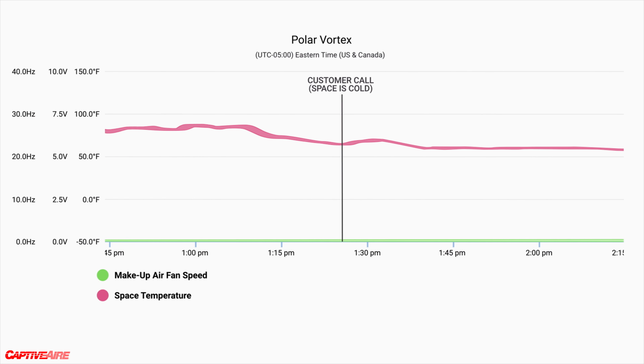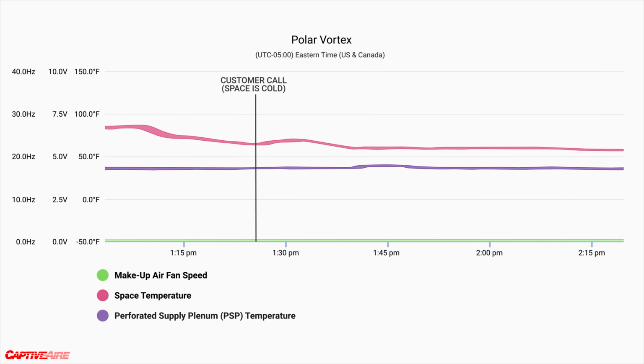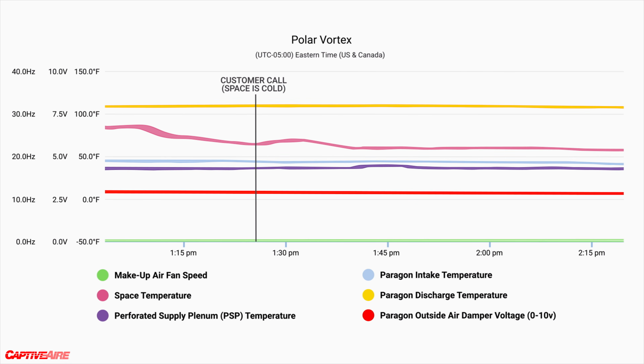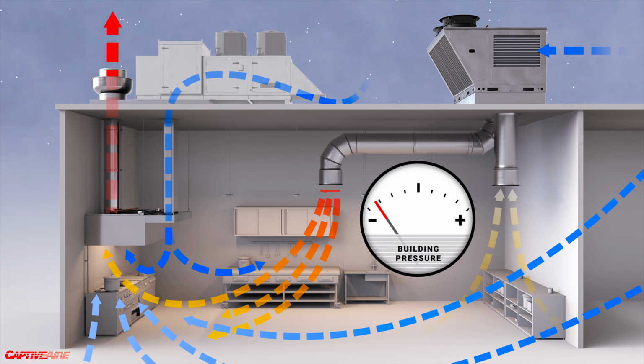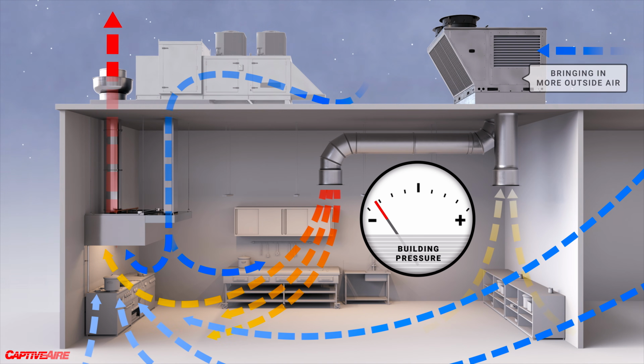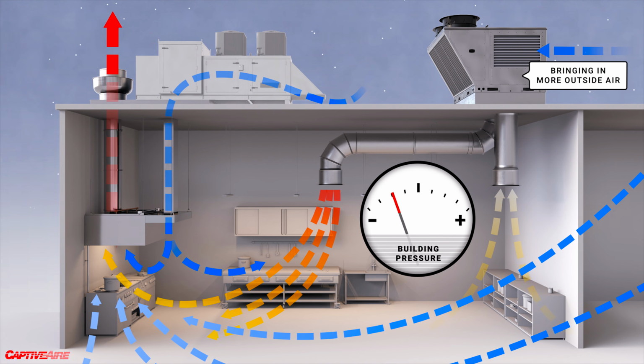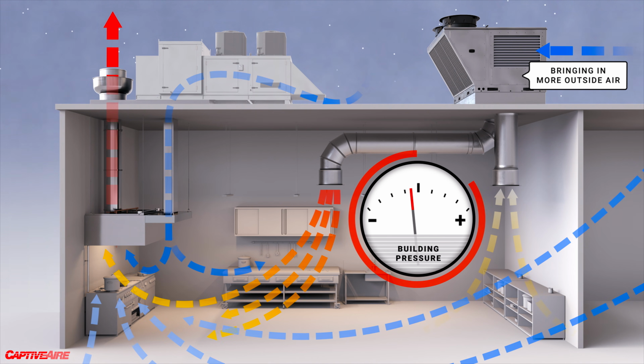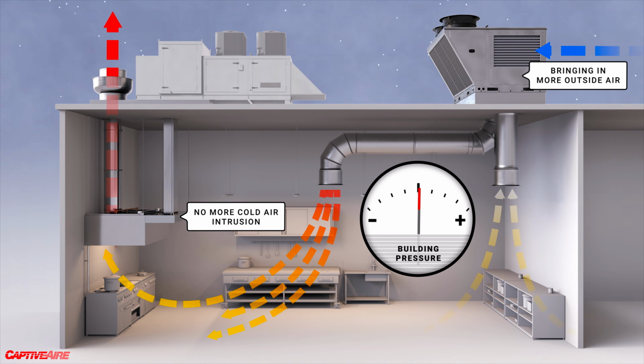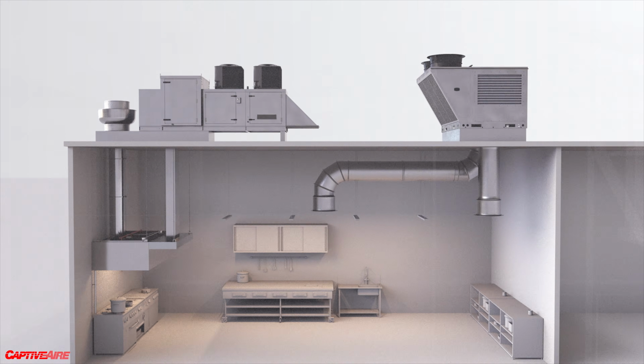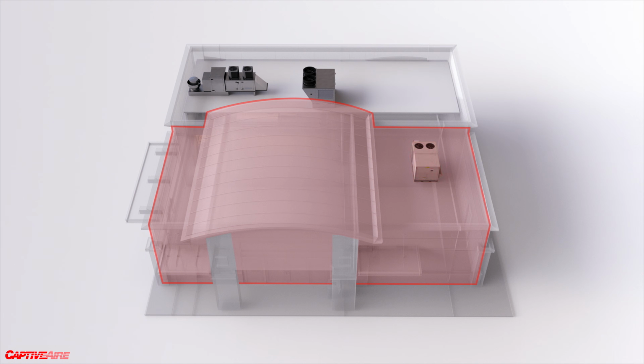So what I did when I pulled this up is I actually pulled up both the makeup air unit, the hood operation, and then our Paragon unit's operation to see what's going on in real time. My goal was to try and reduce that negative pressure as much as I can. So we got a little bit creative here because I can't get out to this site and actually measure where we're getting negative pressure or we aren't. So again, this Paragon unit was designed to run at a certain percentage outside air, not 100% outside air. So my goal was I want to keep increasing the outside air and increasing that damper position to bring in more and more outside air until we get to a point where that building is neutral. And then at that point, hopefully we're not bringing in that super cold air, and that unit serving the front of the space can now maintain the space temperatures better.